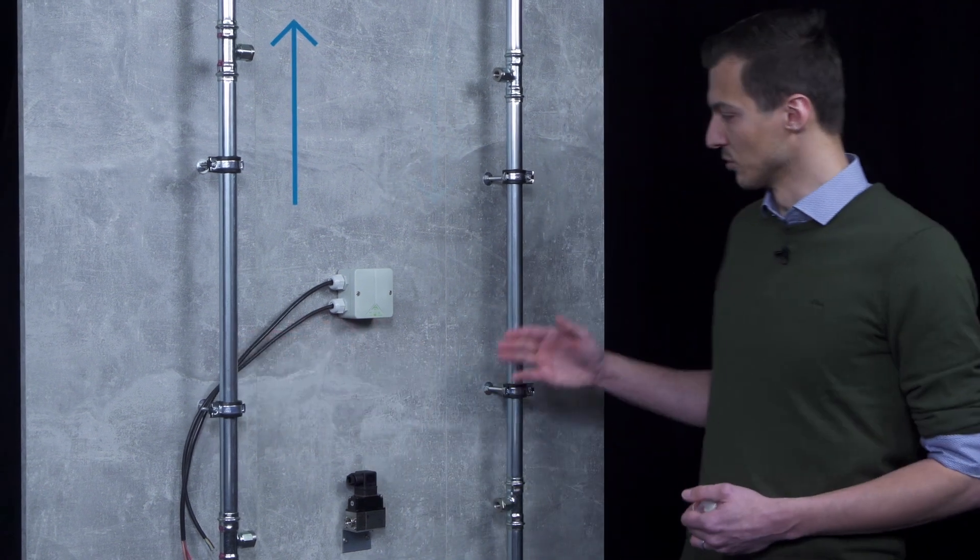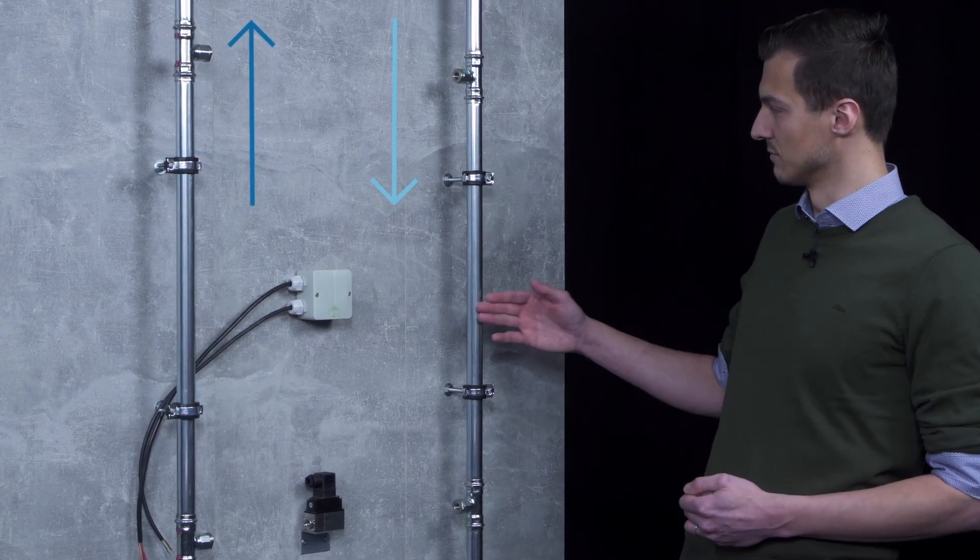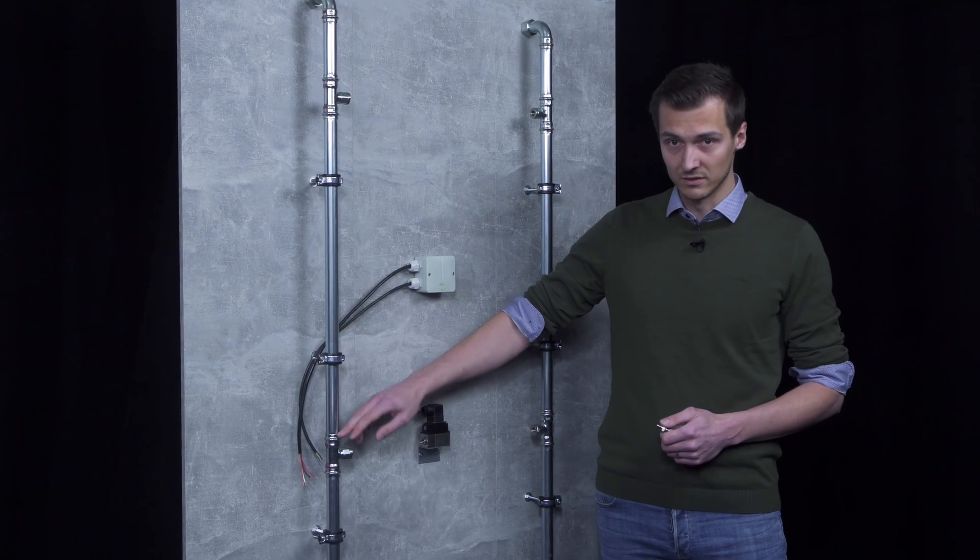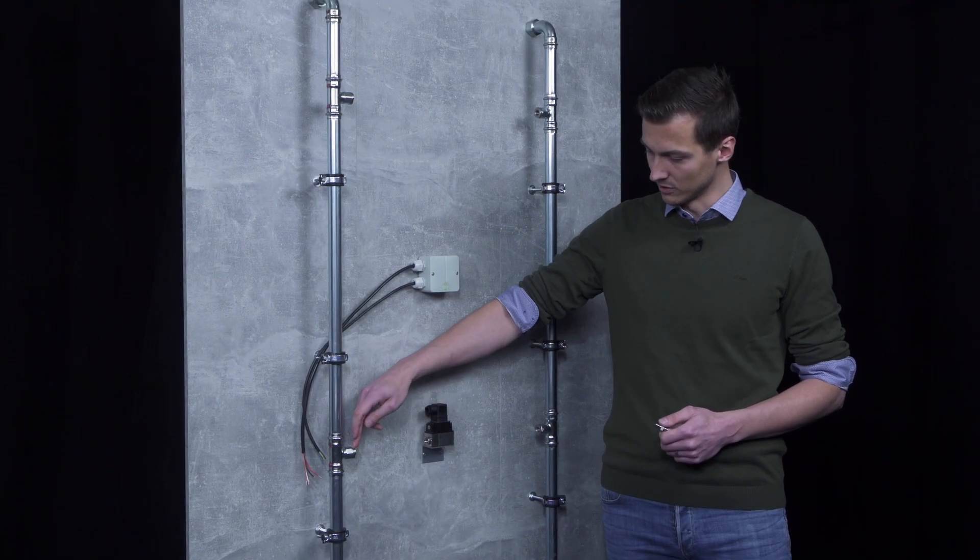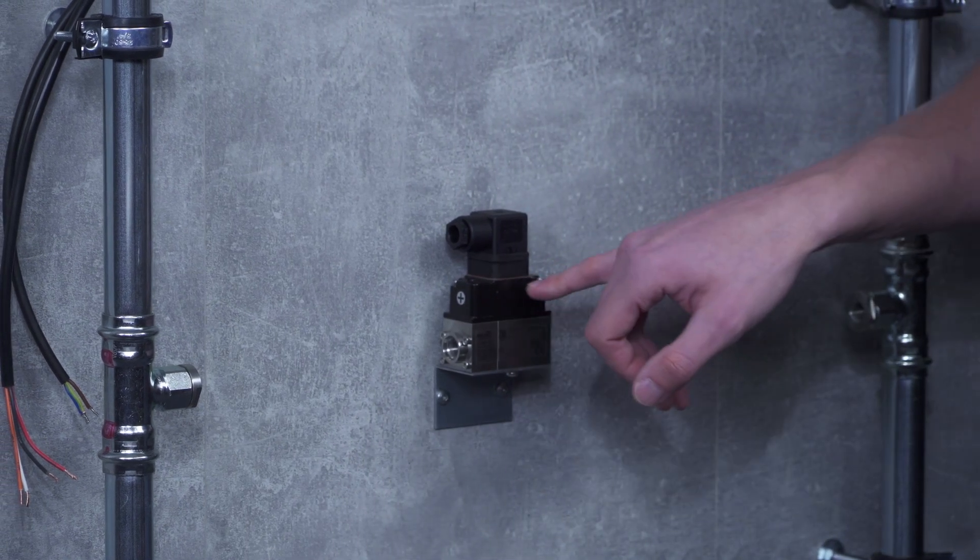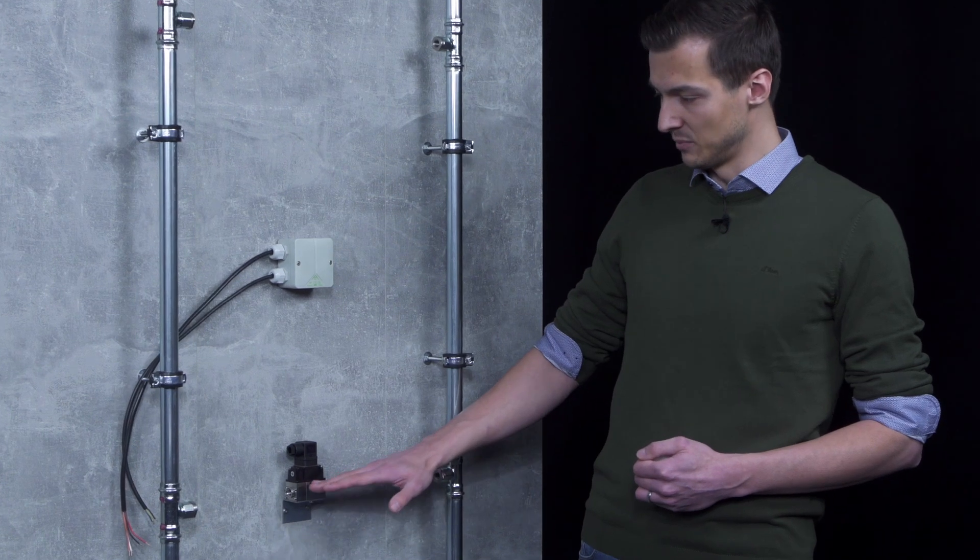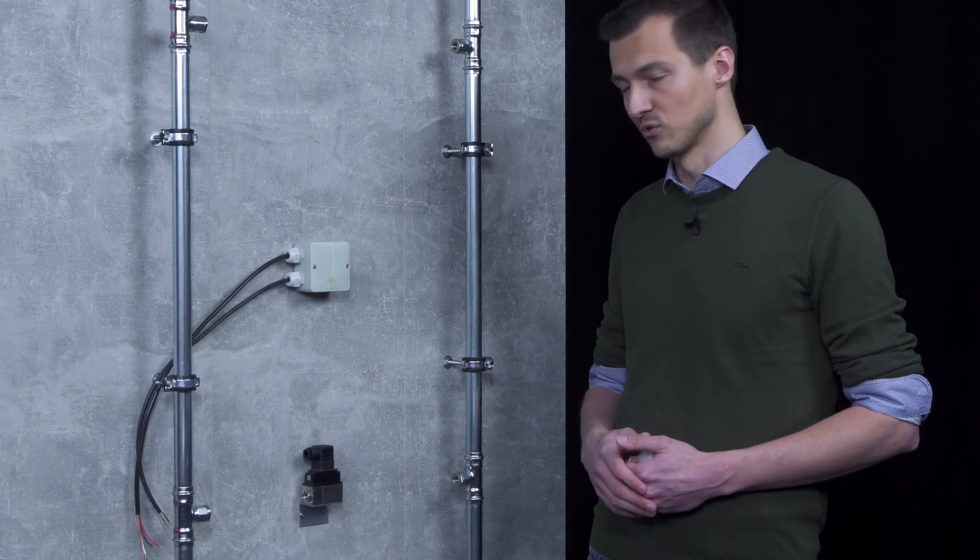To show you how to install our differential pressure sensors, we have prepared a demo wall here. This consists of a supply and a return or a pipe with expected higher pressure and a pipe with lower pressure. We have already fitted matching T pieces here with a quarter-inch internal thread. One thing to note here is the orientation of the WDP, marked by the plus and the minus symbols. The plus should point to the supply or the line with the higher pressure, the minus to the line with the lower pressure. It should also be noted that the WDP is either at the same height as the T pieces or below them to facilitate venting of the system.